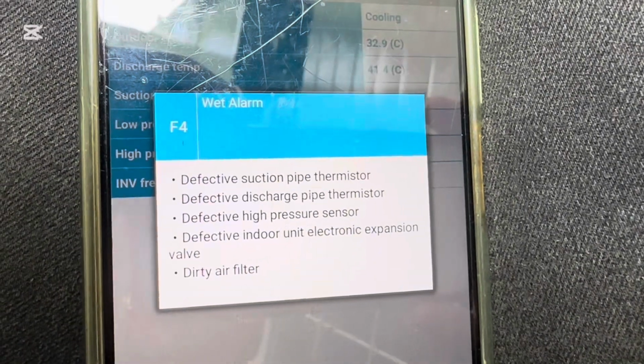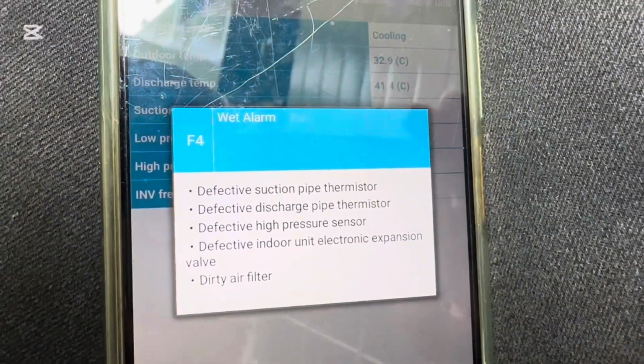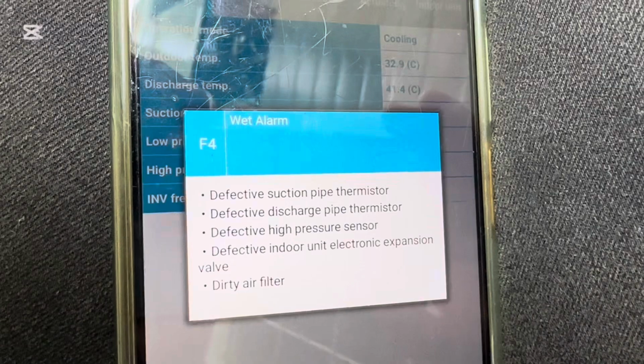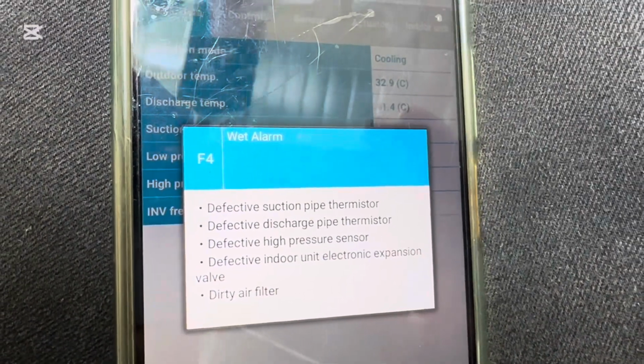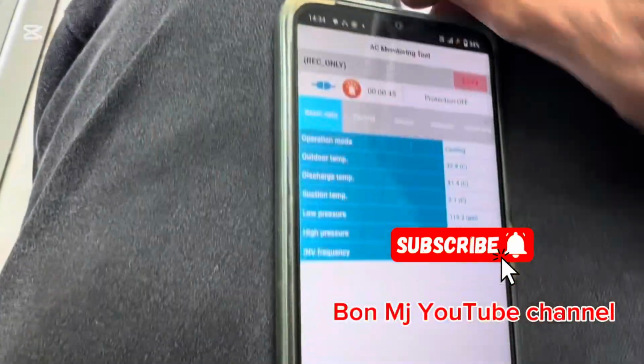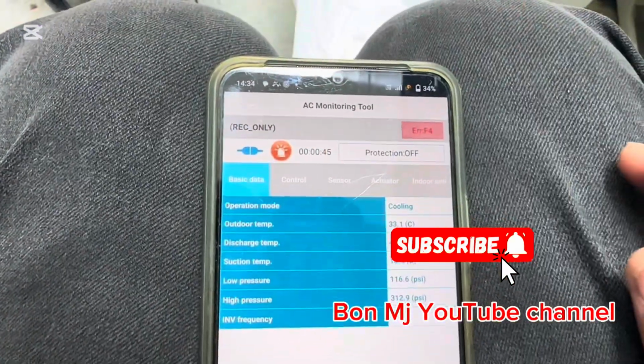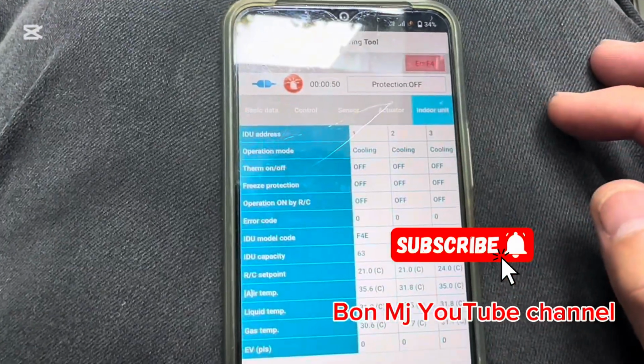Suction pipe thermistor, discharge pipe thermistor, high pressure sensor, defective indoor unit electronic expansion valve or dirty air filter. But this is a new installation. We need to check the indoor units one by one. Okay, we see the indoors, total 18 indoor units.